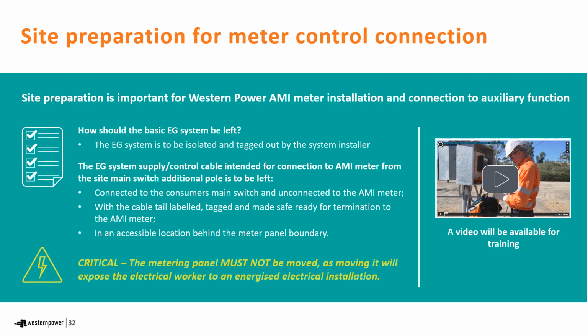So, the site preparation for meter control: how should you leave it? After you've finished your commissioning and testing, you should isolate and tag out this embedded generation system, and that's done by the system installer. We want the supply control cable intended for connection to the AMI meter from the site main switch additional pole connected to the consumer main switch and unconnected to the AMI meter. The cable will be labelled, tagged, and made safe for termination to the AMI meter.